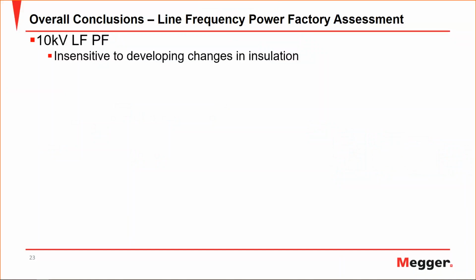So some overall conclusions here. The 10 kV line frequency power factor, bottom line, is insensitive to developing changes in insulation. You saw a perfect example here today where line frequency power factor can look good, but the 1 hertz will look bad and there is a problem with an asset. And if you remember from Robert's presentation with the graph earlier, where he had the 3 plots, he showed definitively that 3 assets can be tested, show similar line frequency results, but then have varying levels of moisture in the transformer.